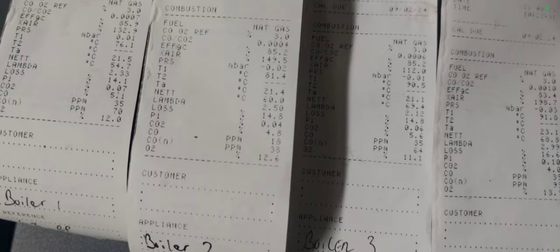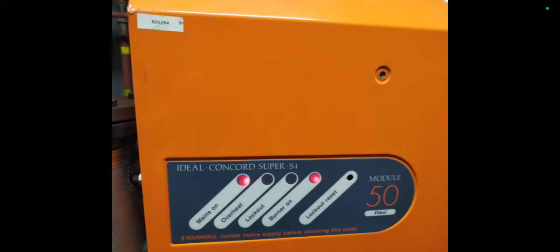And these were my readings for all my boilers. I had some good readings. I was happy with them. It's important that you get these cases on properly, getting the screw back in the right place, because otherwise the indicators won't be easily visible, so you won't be able to see what the situation is. It's annoying that the overheat button is on the left of the case, so once you get the case on, in order to click that overheat button you have to take the case off. I think that was a bad design.